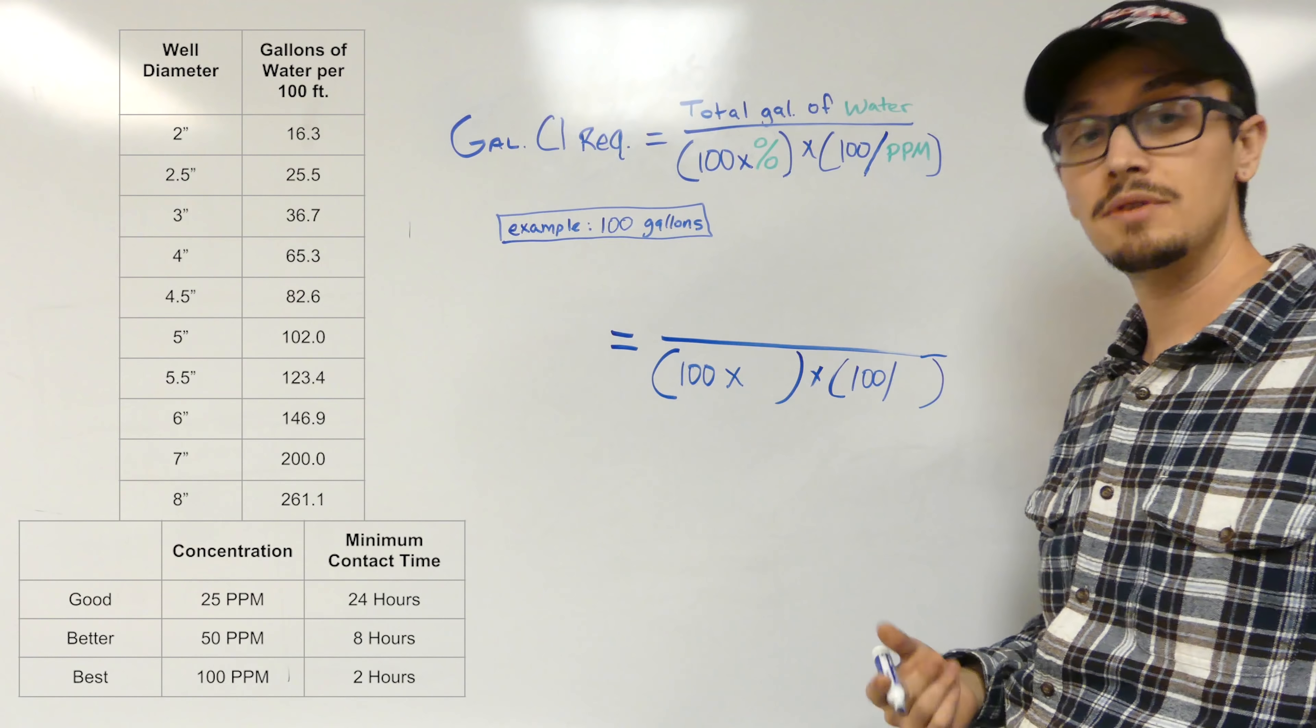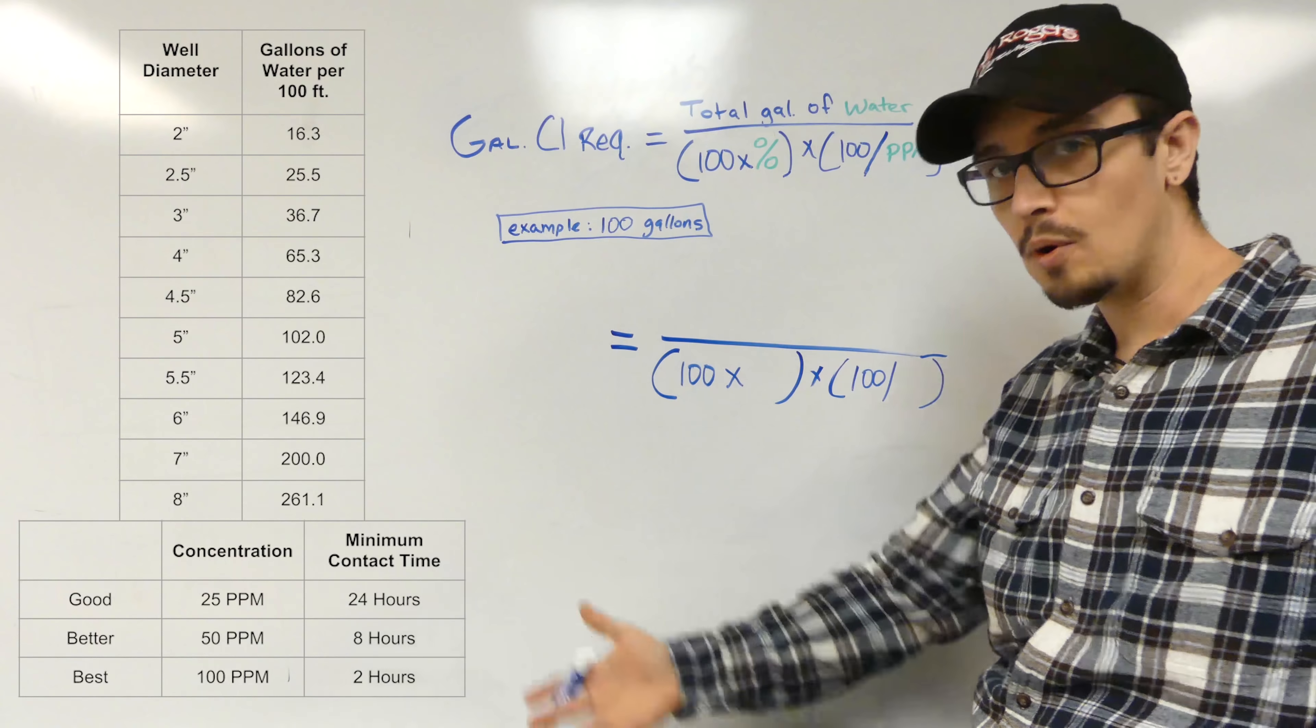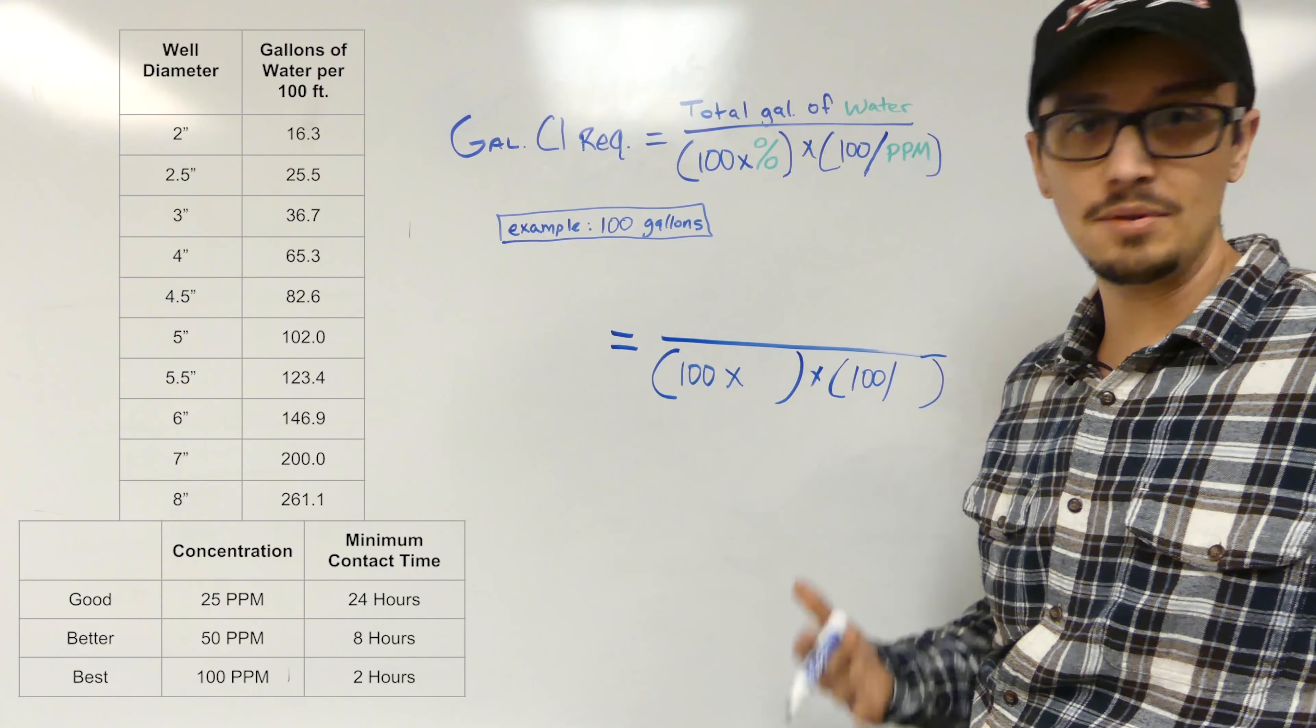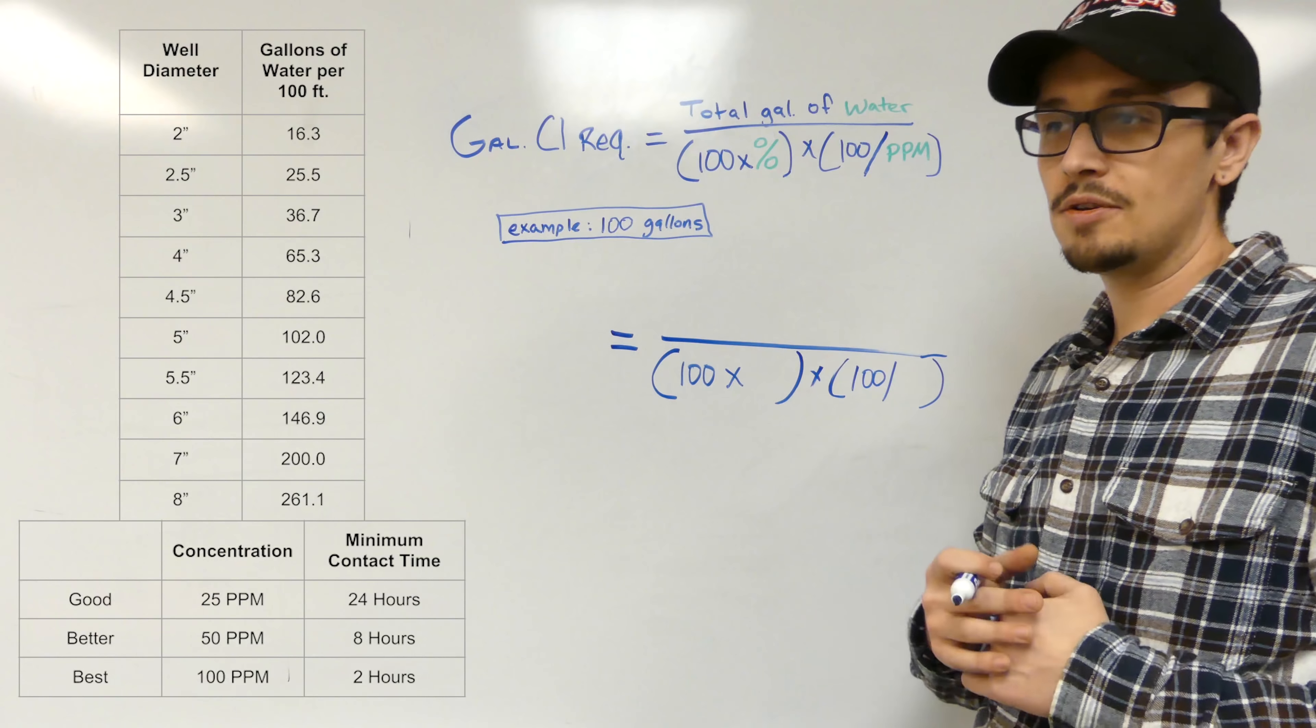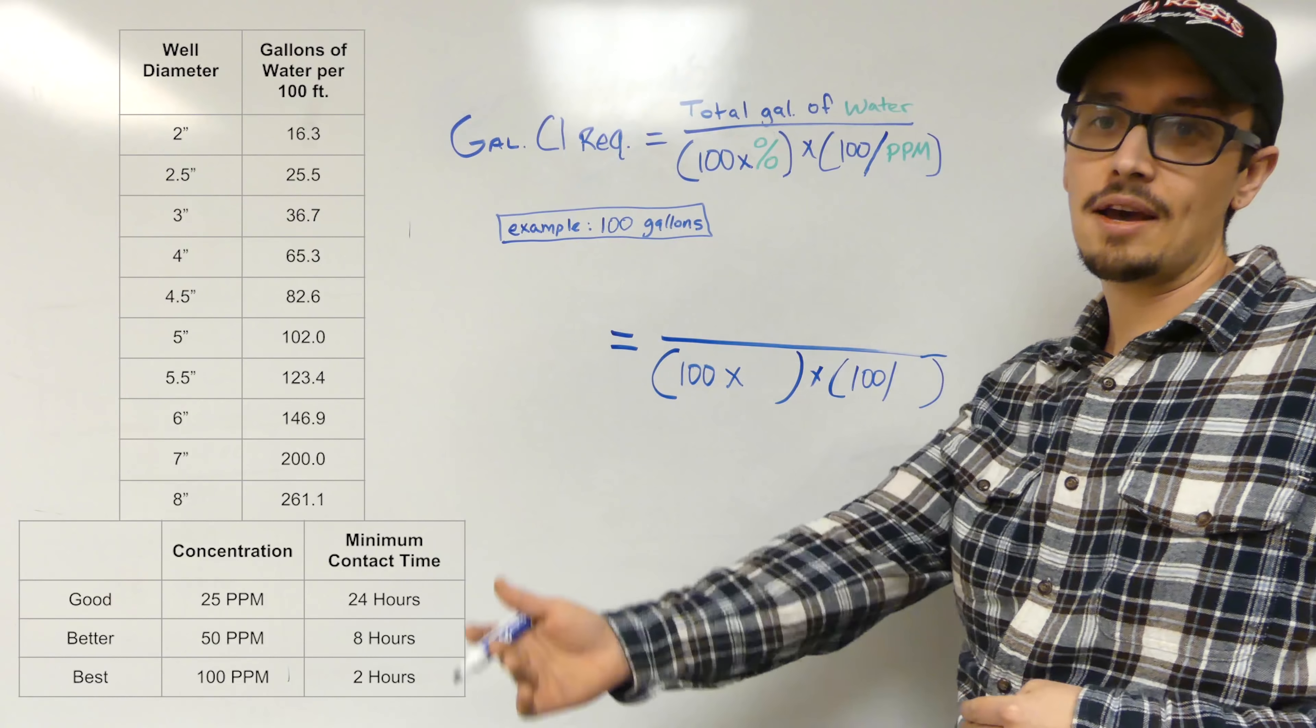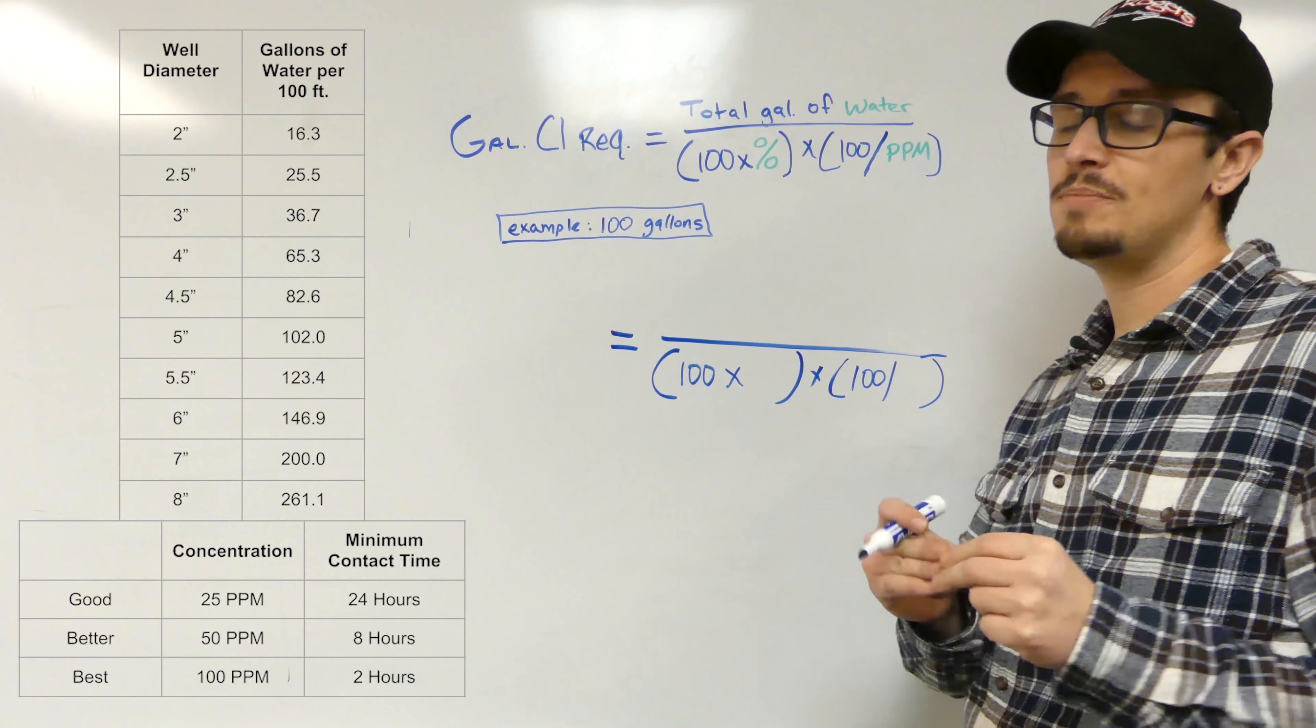Then we multiply that by 100 over the parts per million concentration that we're trying to achieve. Generally with super chlorination or shocking your well, you're looking for between 50 to 100 or more parts per million. You're going to be able to relate that to the contact time and figure out if you've got 8 hours to let it set or you've got a whole day. Obviously most people need their water system and can't be down forever. A high concentration for a shorter period of time is often the better approach. There's other steps involved in this process that can drag it out as well, as far as getting the chlorine out of the water, dumping water on the ground and so forth.